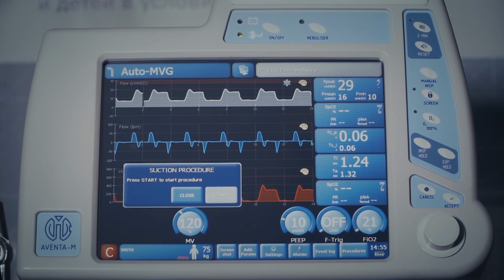During the first stage, the ventilator performs patient pre-oxygenation for 3 minutes by means of increased oxygen content in the respiratory gas. After that, the patient tube may be disconnected from the breathing circuit, and suction procedure may be performed. When the patient is disconnected, the ventilator stops ventilation and switches over to idle mode. At the last stage, after connecting the patient tube to the breathing circuit, the ventilator performs post-oxygenation for 3 minutes.